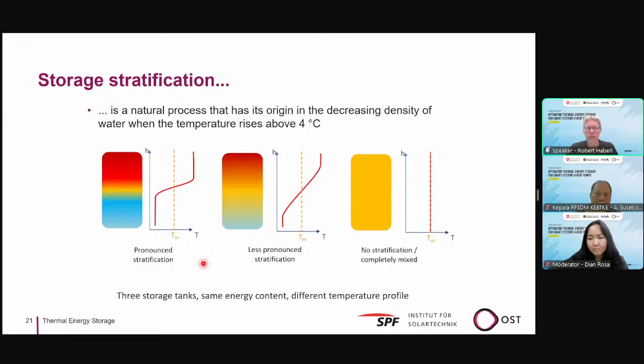So you see here 3 different energy storages. The energy content is the same for all temperature profiles. With the pronounced stratification, the less pronounced stratification, or the no stratification, the completely mixed tank. The average temperature is always the middle temperature. The exergy content varies, meaning the useful energy related to the temperature where it should be used. And the exergy content is highest with the good stratification, and then lower with the less pronounced stratification, and there we have no exergy storage at all because it's not useful if it's fully mixed.